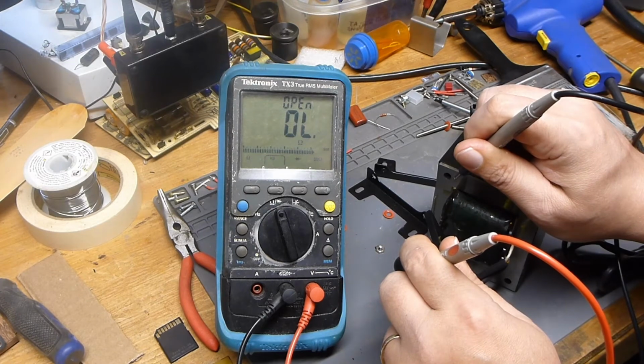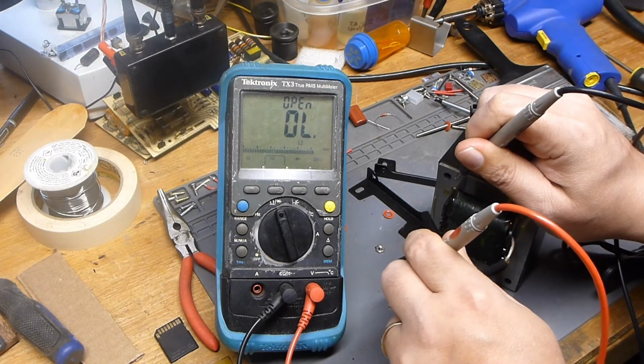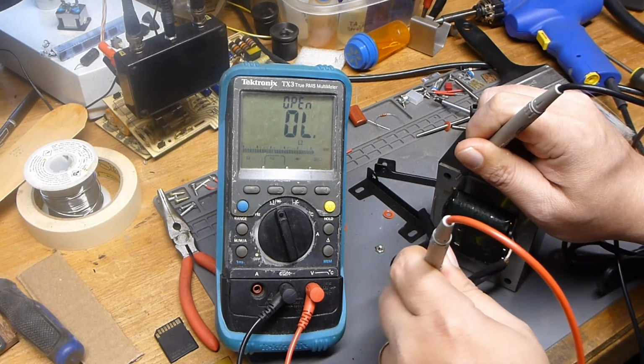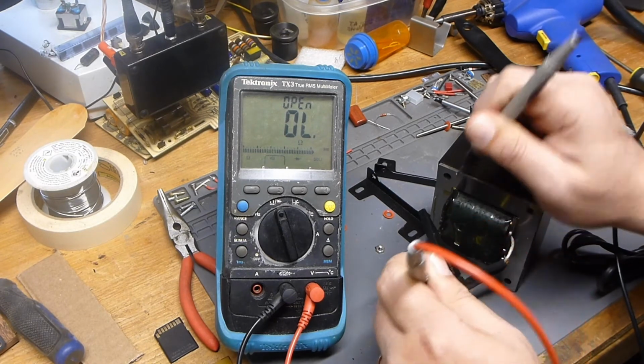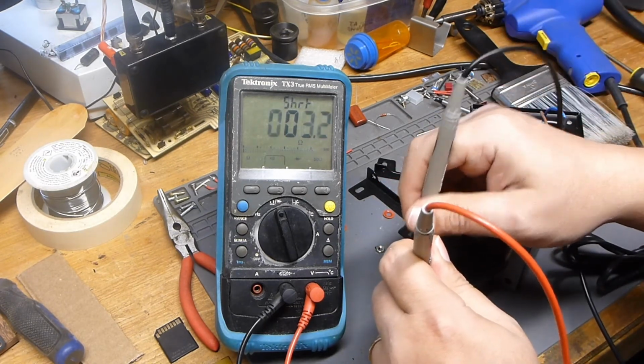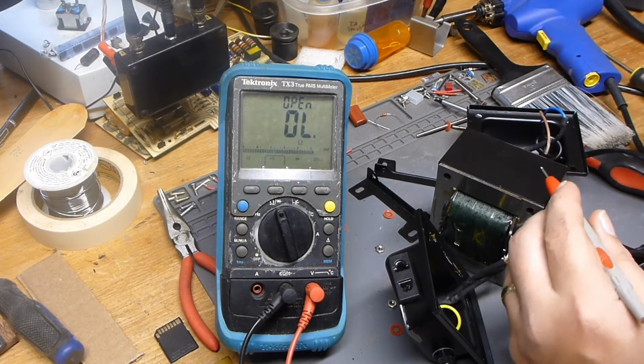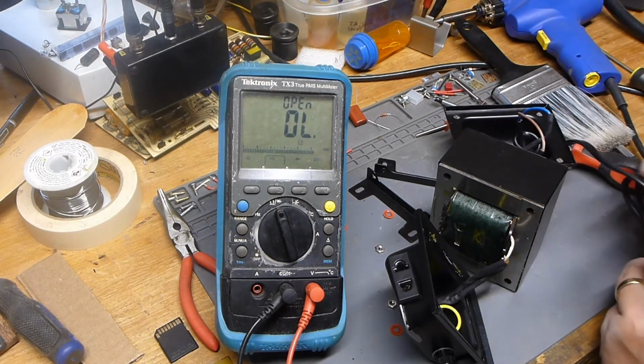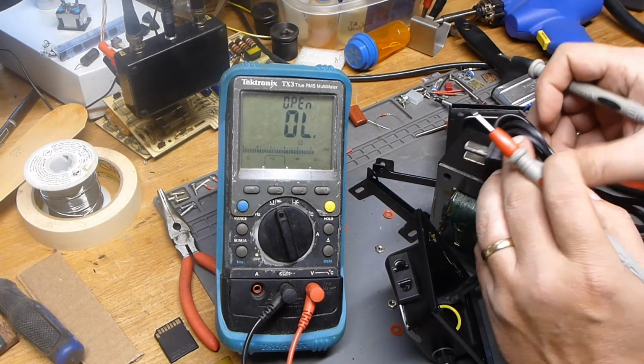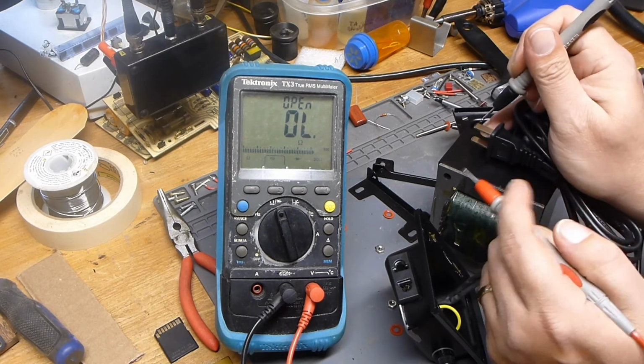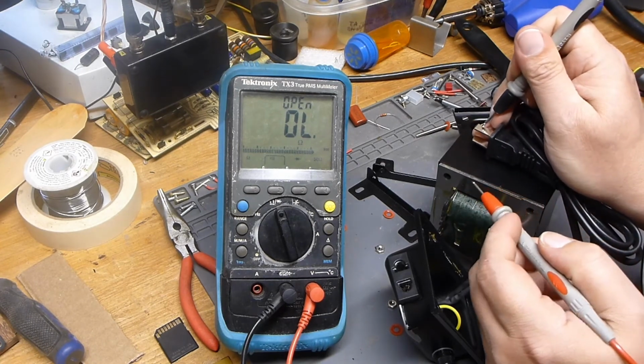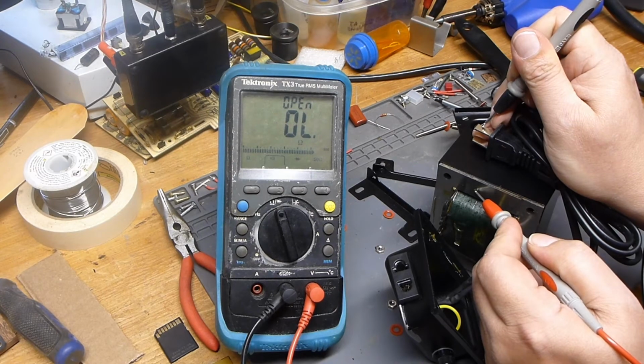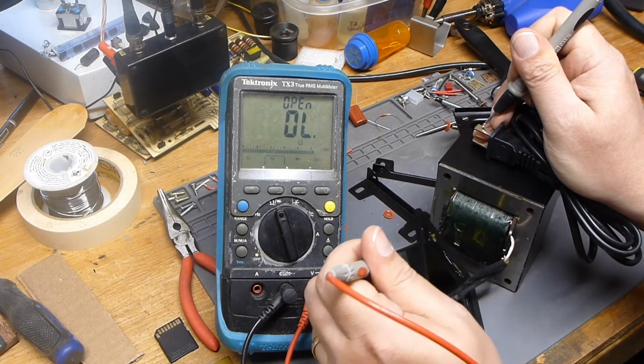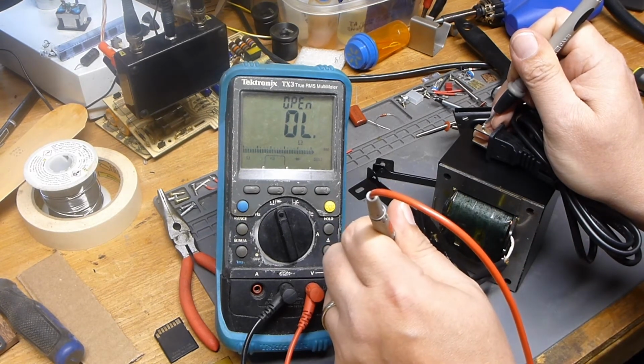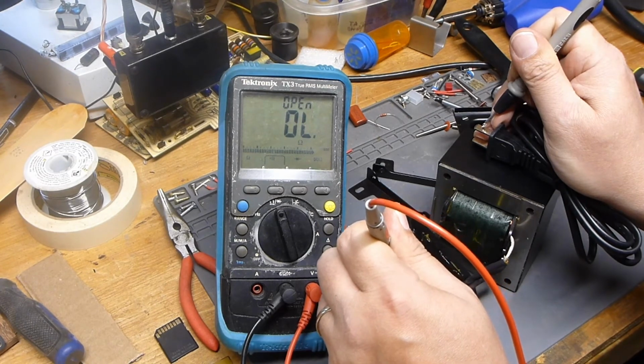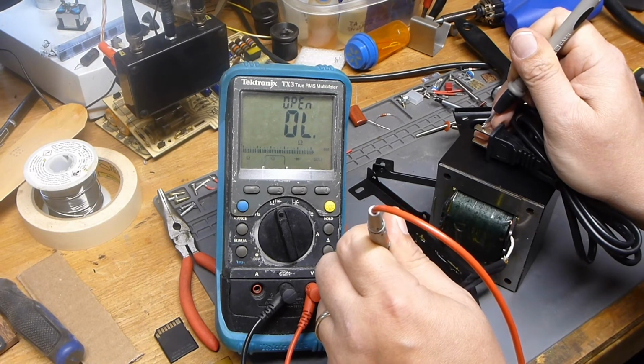No, we do not. So check the other side. Of course, we're not going to have anything. And then if we do the same on the other side, we can go right to the plug and look for a short to our transformer. There's nothing. And then last but not least, we're going to go coil to coil, checking to see if there's any continuity between the two coils, and there is not.